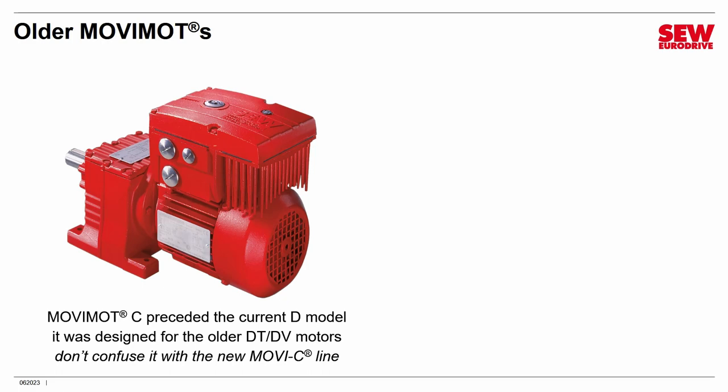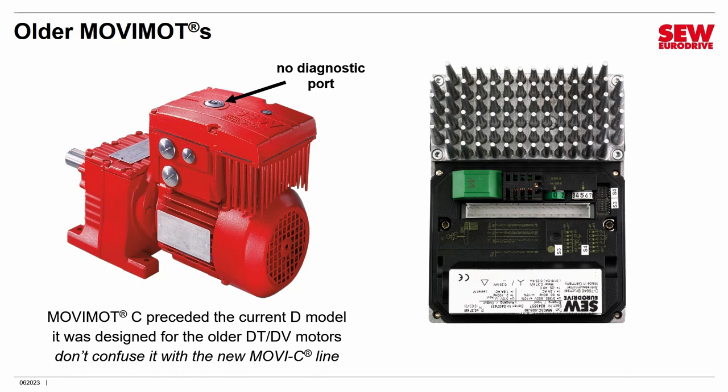How do you tell a legacy version C MOVIMOT apart from the current D version, since they look very similar? Very easily: there is one glaring difference — there is no diagnostic port on the old one. There's only one plug on the top, covering the F1 dial. There's no way to connect it to a PC or a keypad. So if you see one port, it's an older one; if you see two ports, it's the new MOVIMOT D. The control head is also a bit different underneath — there is no DIM module socket, and the DIP switches are in a different position.